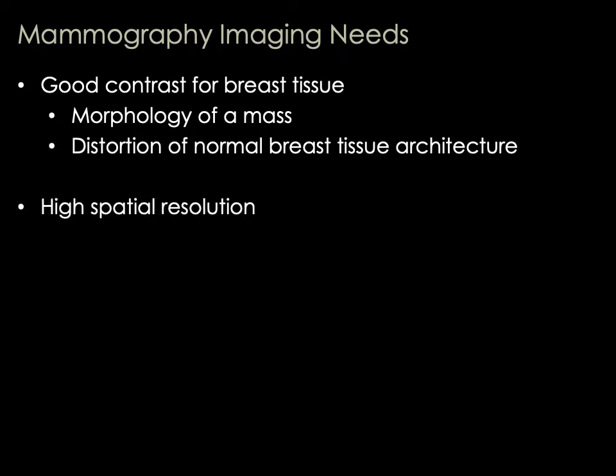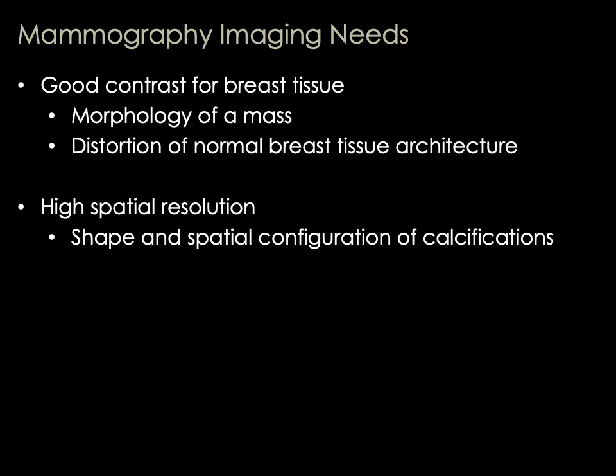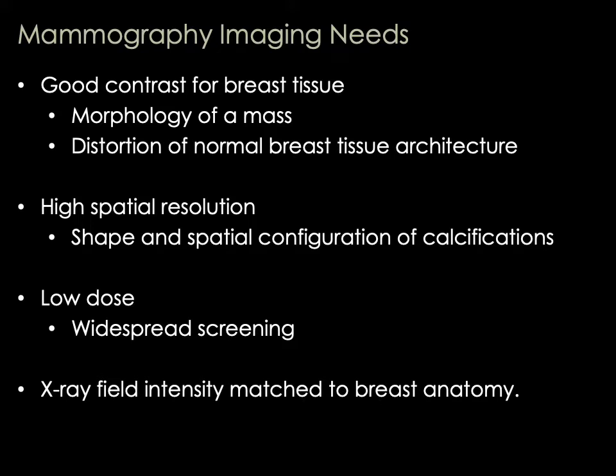The second thing we need is high spatial resolution. This allows us to determine the shape and spatial configuration of calcifications, which can be very small. The third requirement comes from the use of mammography as a screening tool. Since mammography is used for widespread screening of mostly asymptomatic patients, we have to ensure that the dose is low enough that the potential benefit still outweighs any risk. Lastly, we want the x-ray field intensity matched to the anatomy of the breast.